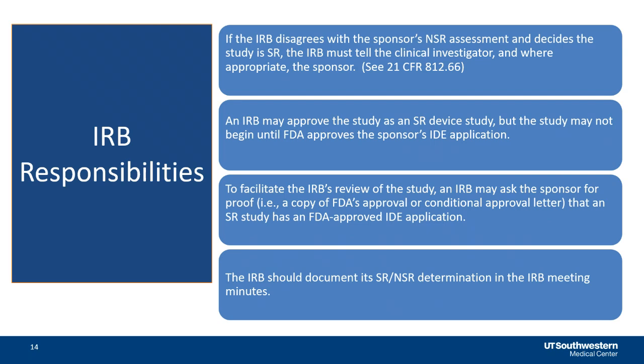I have previously witnessed this occurrence at an IRB meeting at a previous employer, and as you can imagine, the situation creates significant delay in the approval of a study. It behooves researchers who are serving as a sponsor investigator to request FDA consultation prior to submission to the IRB when there may be a question about whether a device is a non-significant risk device.